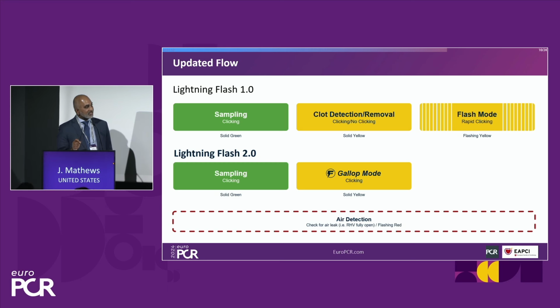The blood loss paradoxically is less than you see with Lightning 12. So even less blood loss, even with a larger bore catheter. The gallop mode is when you're within thrombus. By switching back and forth, you're able to do these cases a lot more efficiently. If it goes red, that means you have air in the system. And I'll tell you that our case times have dropped dramatically.